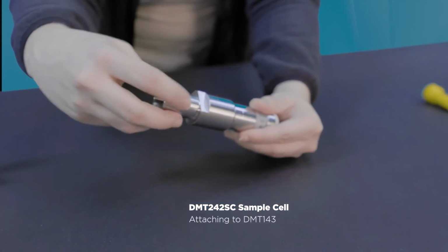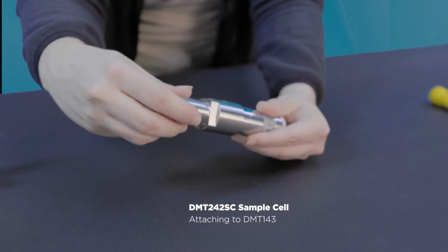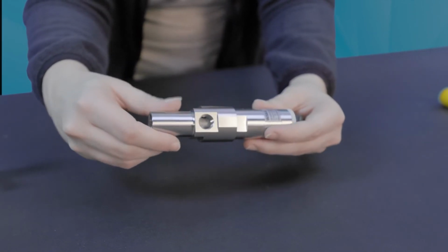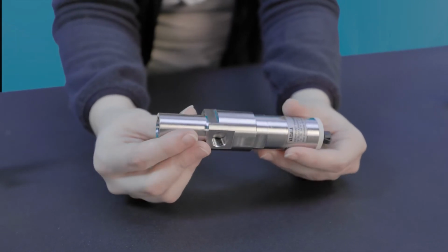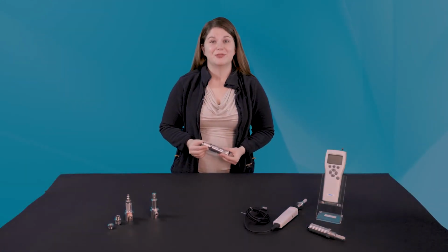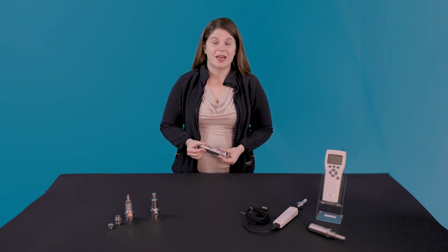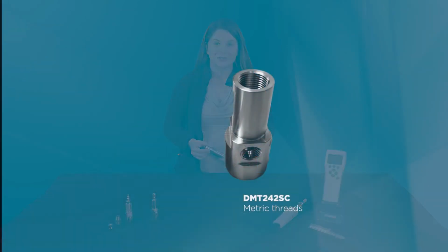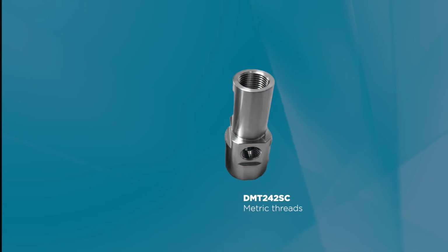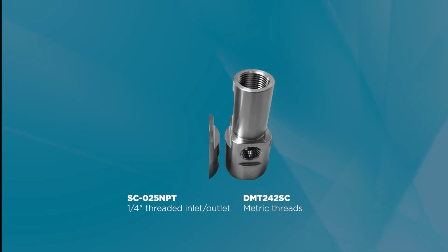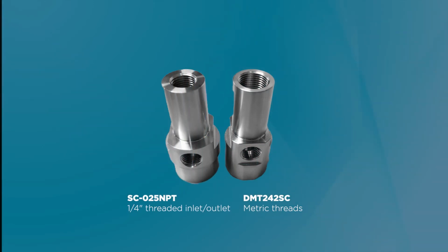Here I have the DMT242SC sample cell, which I will attach to this DMT143 dew point transmitter. And as you can see, once installed, the sample cell provides a threaded inlet and outlet. This sample cell is a great option if you plan to design a custom installation with appropriate pipe design and any necessary valves or flow meters. The DMT242SC sample cell connections are metric threads, but we also offer an equivalent sample cell, part number SC-025NPT, that provides a 1/4-inch female NPT connection for both the inlet and outlet of the cell.